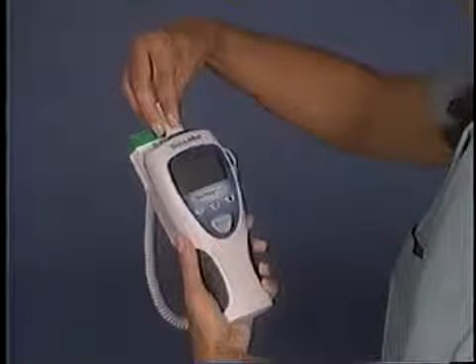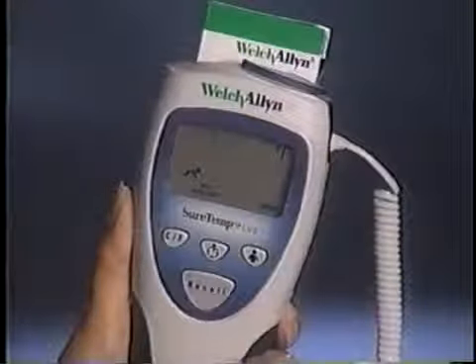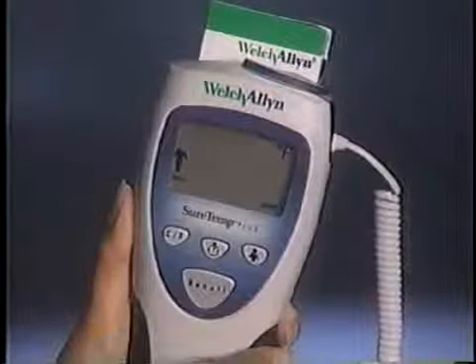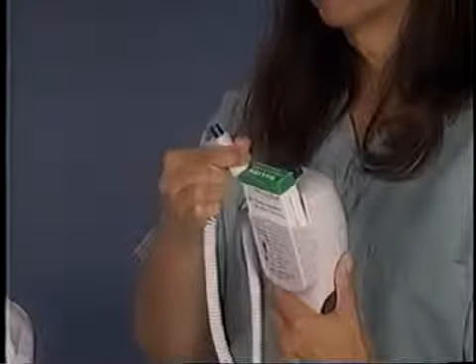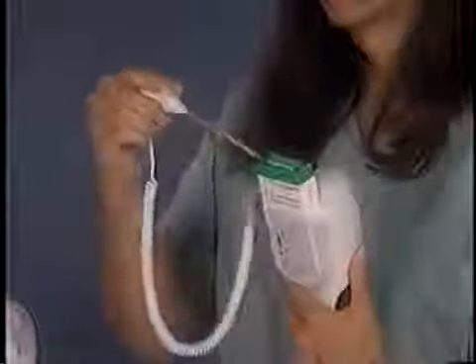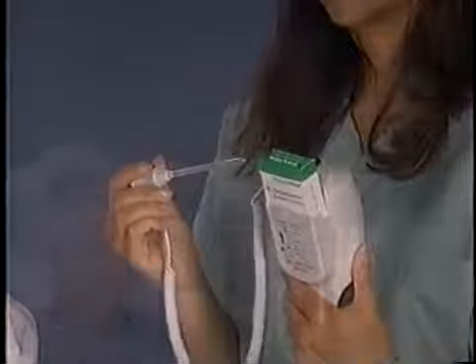Use the probe with the blue ejection button and the blue probe well when taking an oral temperature. Hold the probe handle collar with your thumb and forefinger, being careful to avoid holding or pressing the ejection button, and withdraw the probe from the well. Verify that oral mode is selected. If this indicator is not displayed, press the Mode Selection button until it appears. Insert the probe into a Welch Allyn probe cover, pressing the probe handle down firmly. The ejection button pops up when the probe cover is properly seated.